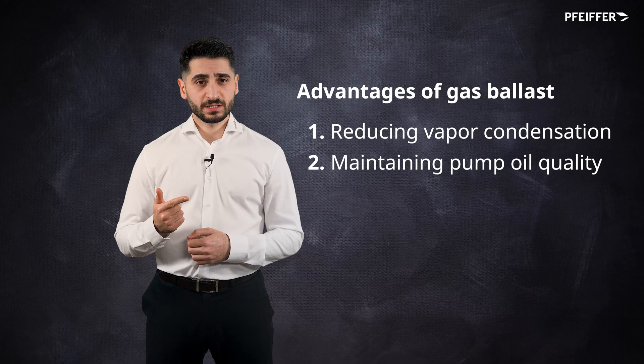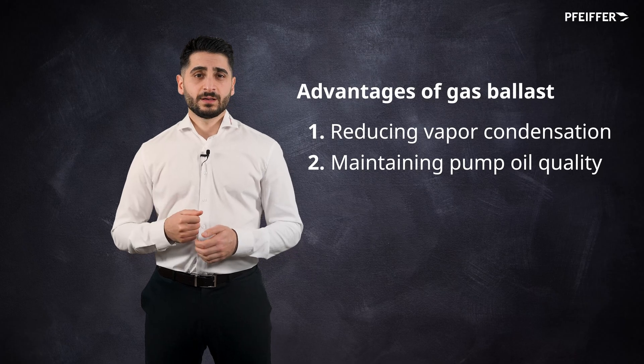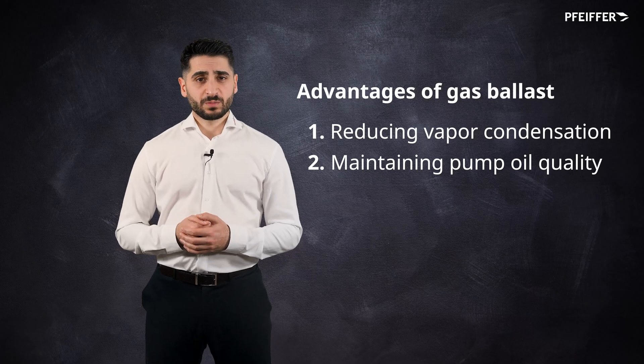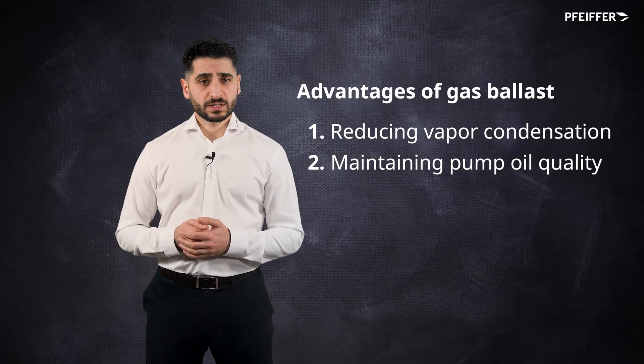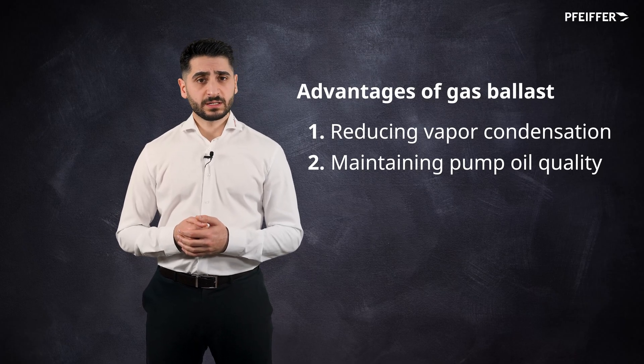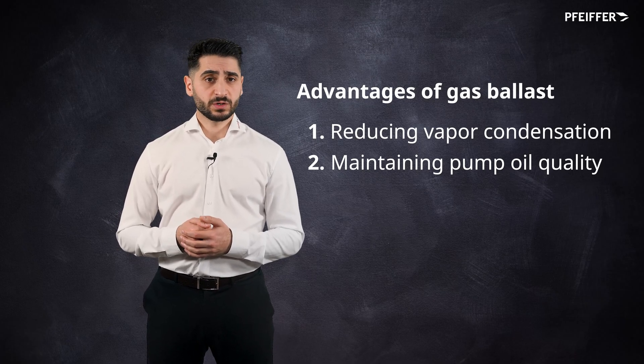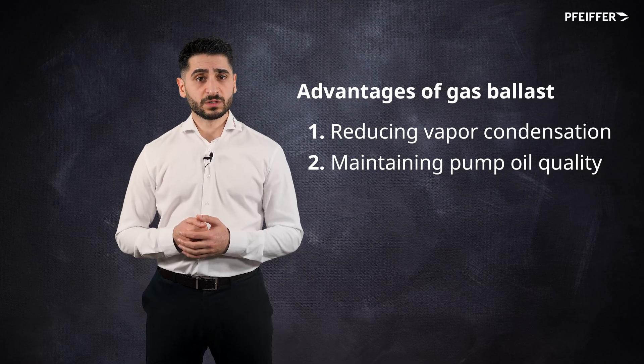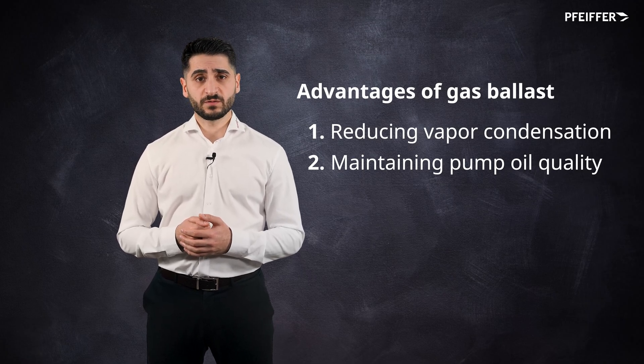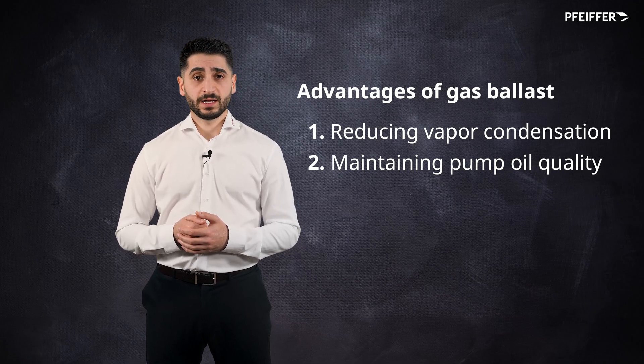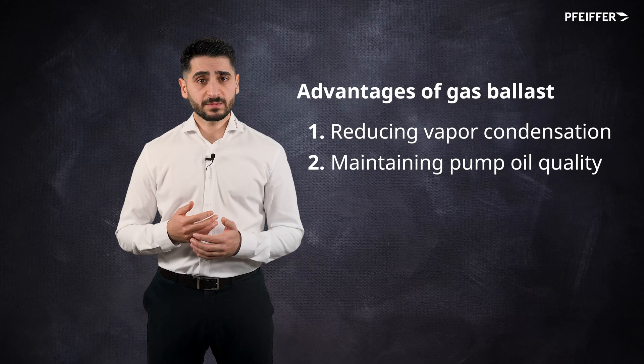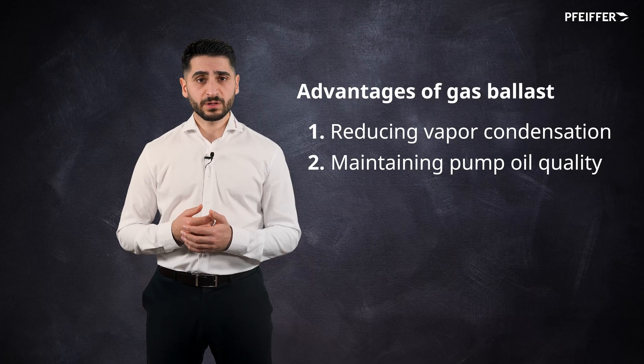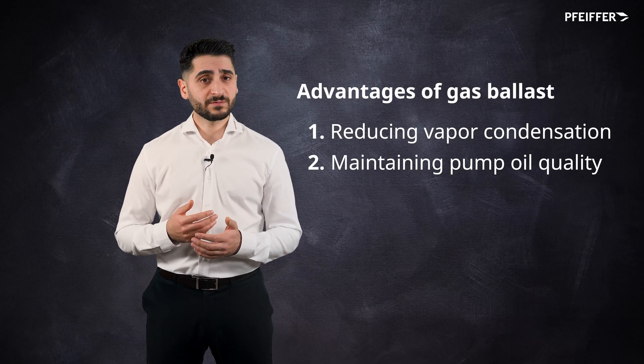Maintaining pump oil quality is another advantage. In many vacuum pumps, oil is used as a lubricant and as a sealant in certain pump designs. Condensed vapors can contaminate and degrade the quality of the pump oil. Gas ballast helps maintain the integrity of the pump oil by minimizing vapor condensation.